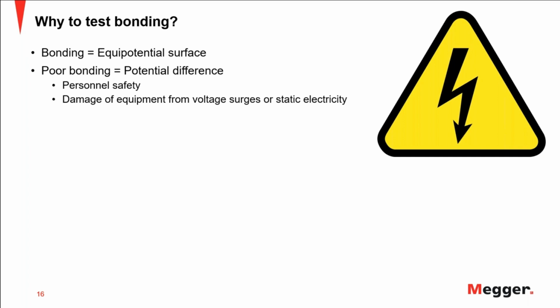If there's a connection to a voltage source, you want that equipotential surface, because if you don't have it, there's going to be a potential difference, and that is going to cause circulation of current between the surface and ground, or whoever touches that. So it can affect personal safety, or it can damage equipment from voltage surges or static electricity. If for any reason any part that is intended to be grounded has a potential difference, that becomes a safety hazard. The other big purpose of having an equipotential surface is to have a proper path for lightning protection systems.